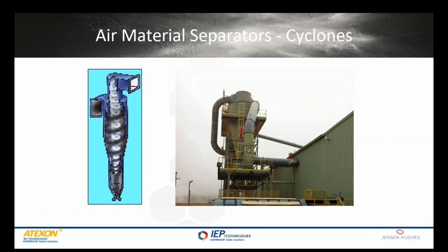Another type of vessel used at biomass facilities for separating particulate from the airstream is cyclones. Cyclones basically have the same type of explosion risks that you would find in a dust collector. Cyclones are a bit more of a challenge for explosion venting, since having a flat vent on a cylindrical vessel that's using tangential force to separate dust can mean some inefficiencies in your dust separation. But explosion venting can be used if put up above the vortex finder or up on the shoulder of the cyclone. Otherwise, explosion suppression would probably be the main explosion protection method employed.